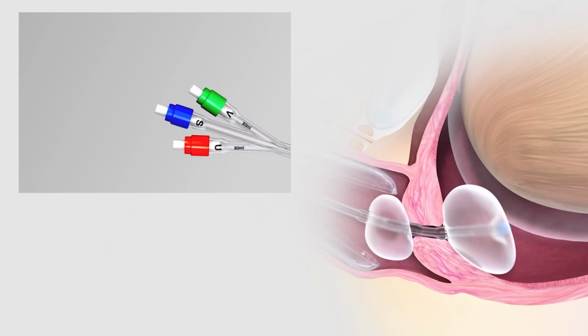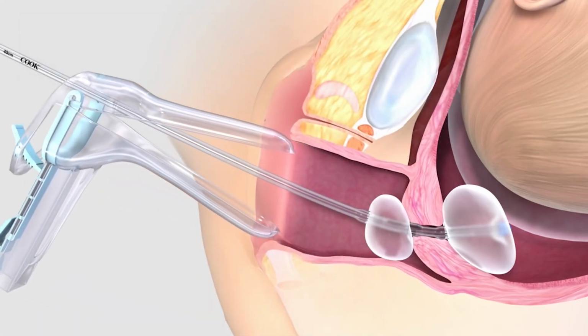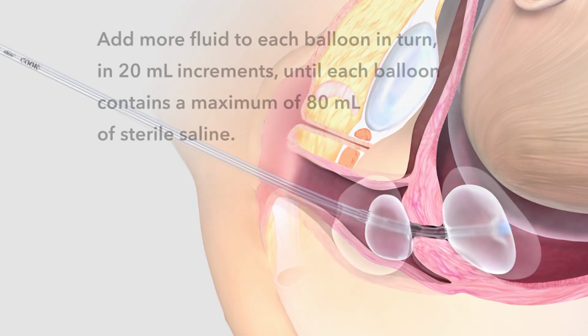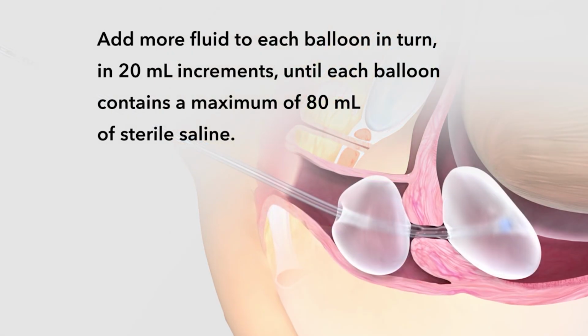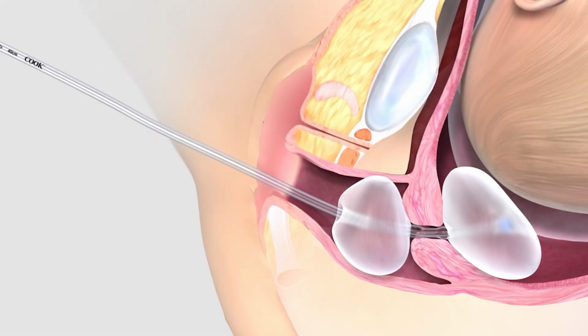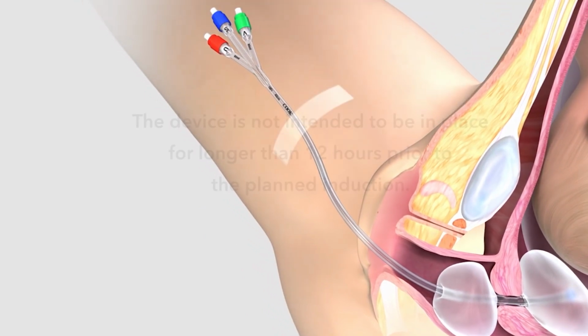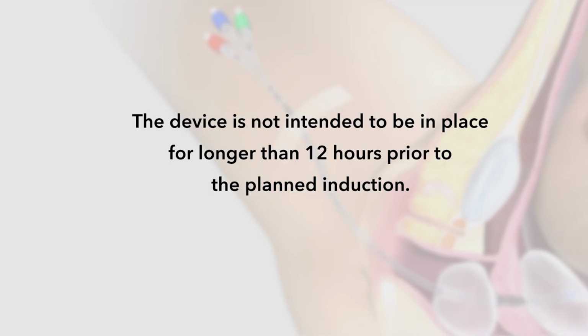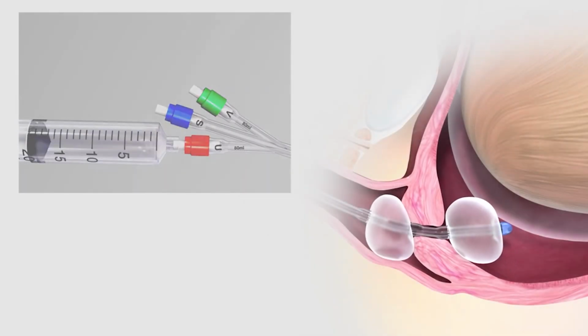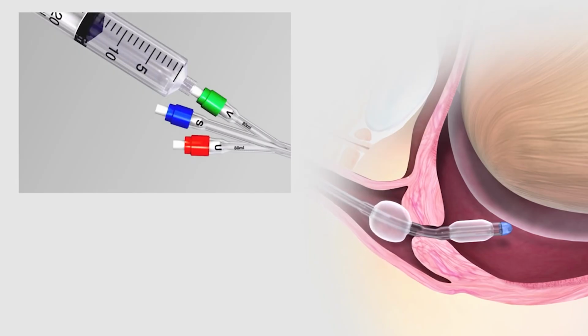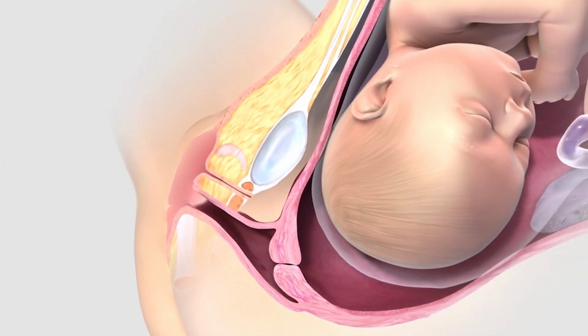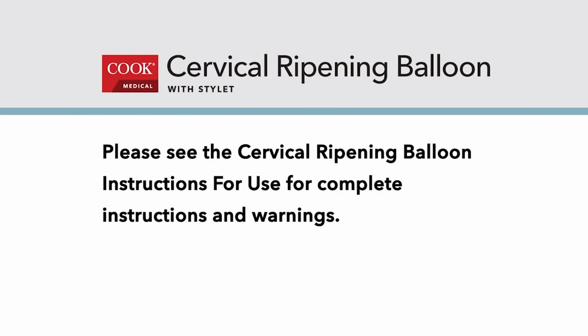Once the balloons are situated on each side of the cervix and the device has been fixed in place, you may remove the speculum. Add more fluid to each balloon in turn in 20 milliliter increments until each balloon contains a maximum of 80 milliliters of sterile saline. Take care not to overinflate the balloons. If necessary, the proximal end of the catheter can be taped to the patient's thigh. Please note that the device is not intended to be in place for longer than 12 hours prior to the planned induction. To remove the device, deflate both balloons through the corresponding valves marked U and V and remove vaginally. Please see the cervical ripening balloon instructions for use for complete instructions and warnings.